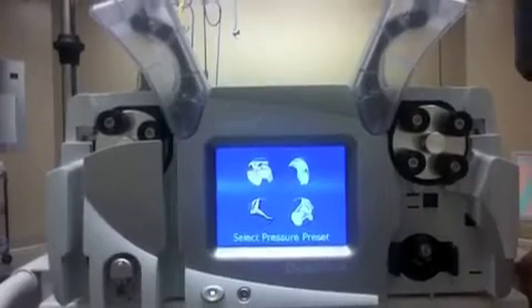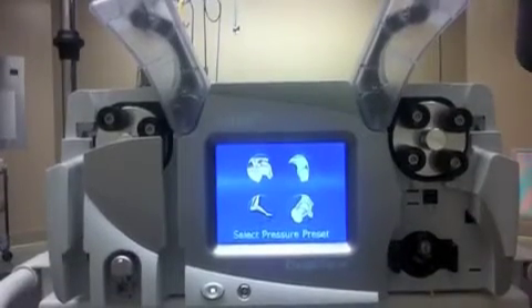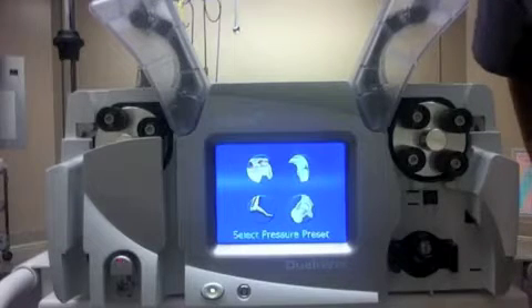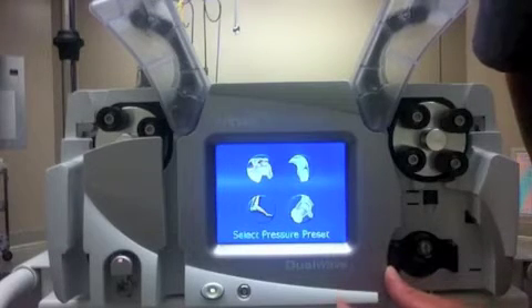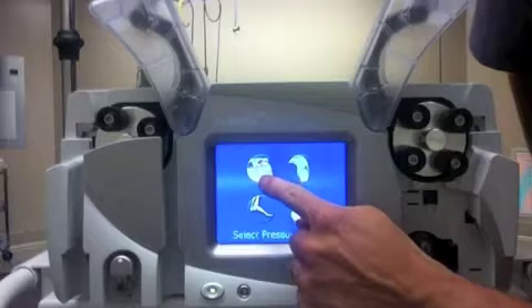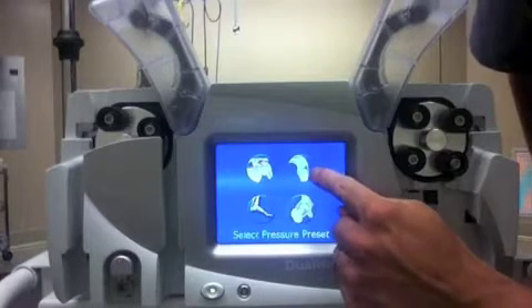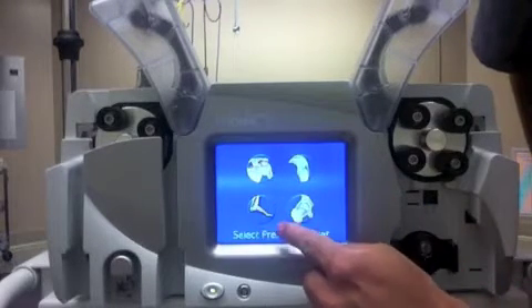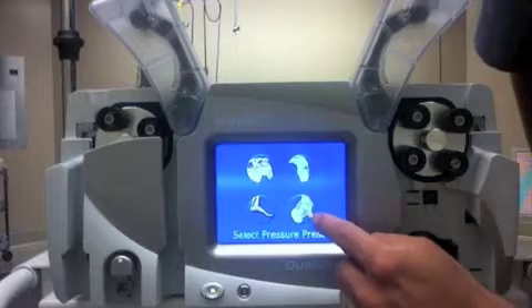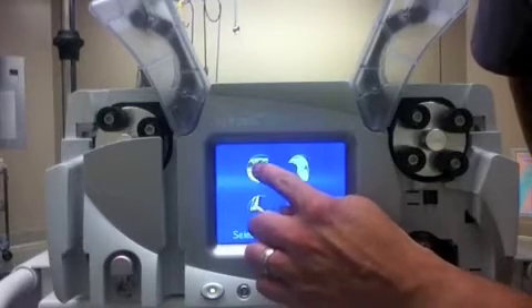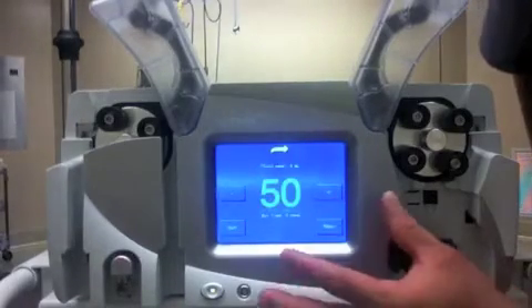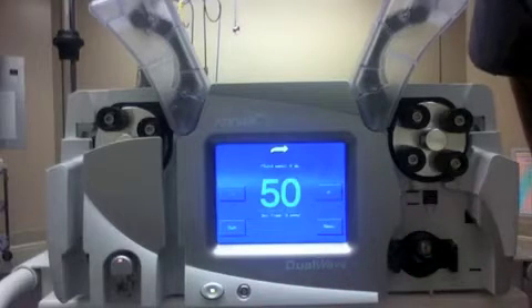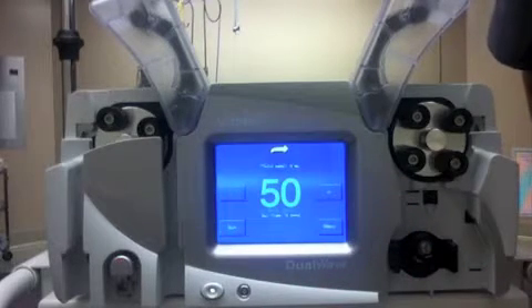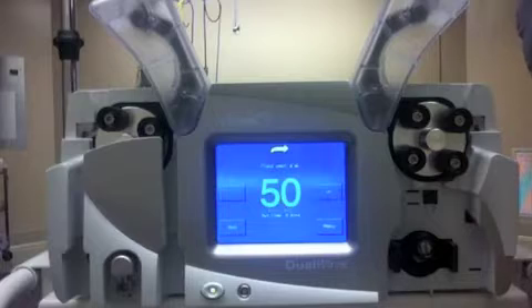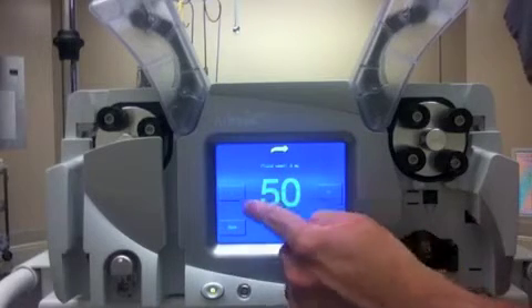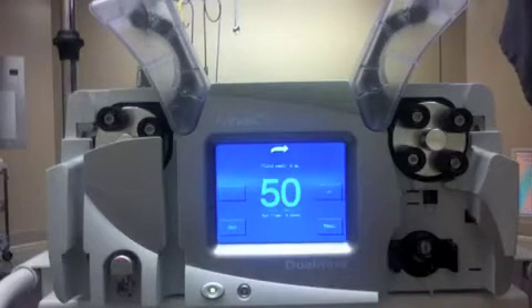After having connected the shaver handpiece to the shaver console, select the proper joint on the display for the Dualwave pump. To the top left is a shoulder, there's a knee, an ankle, and a hip. Let's imagine we're doing a shoulder. So we would hit the shoulder. It would take you to your default pressure setting depending on the joint selected. Of course, you can go up or down with the plus or minus per doctor preference.